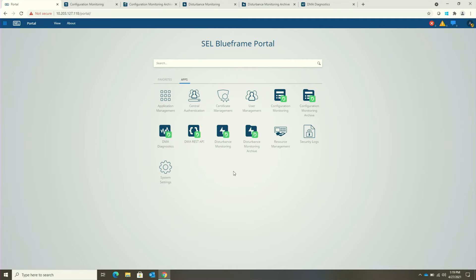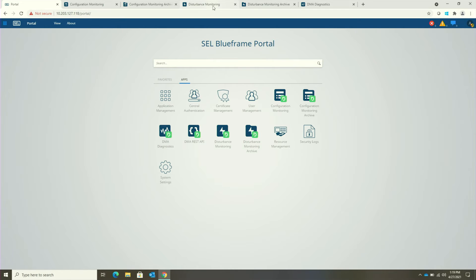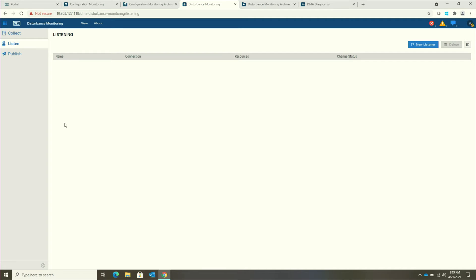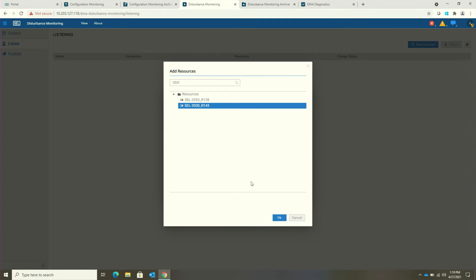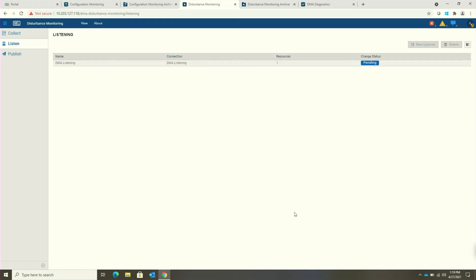Another application package in DMA is disturbance monitoring. Disturbance monitoring includes the configuration application for defining the plans to go out and collect oscillography and sequence of events information from your configured devices on the schedule that you set. Additionally, disturbance monitoring supports the ability to listen to SEL R-TACs for a notification that there's new data available. We can define an R-TAC device already set up in the system and tell it to listen, and now the system will listen to this R-TAC for any notification that new data is available for collection.